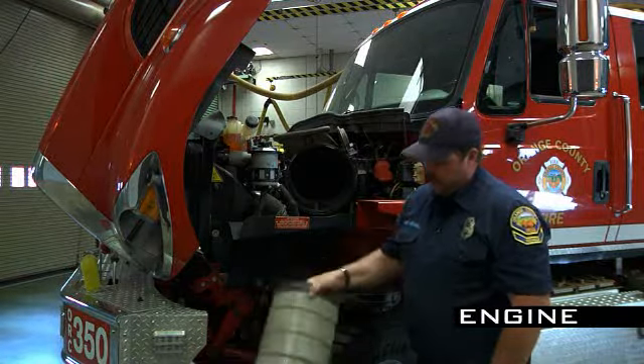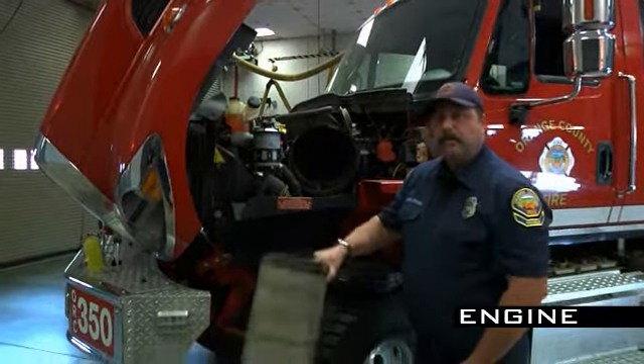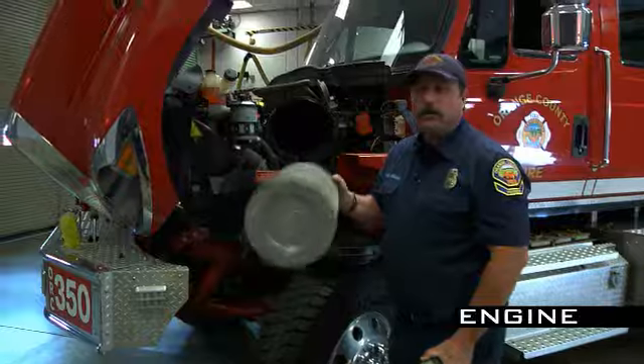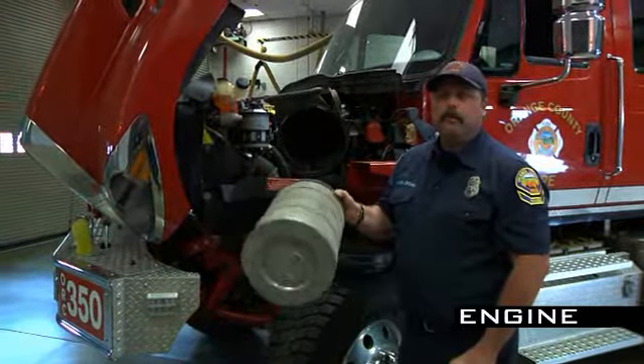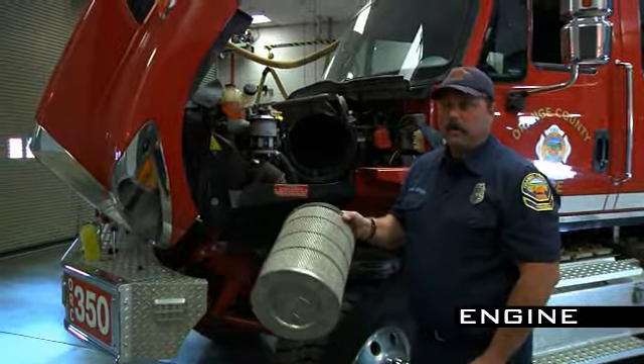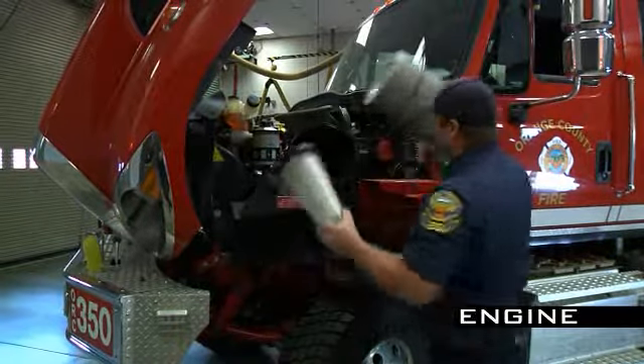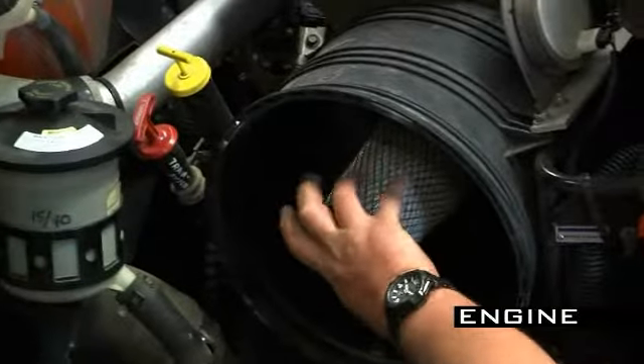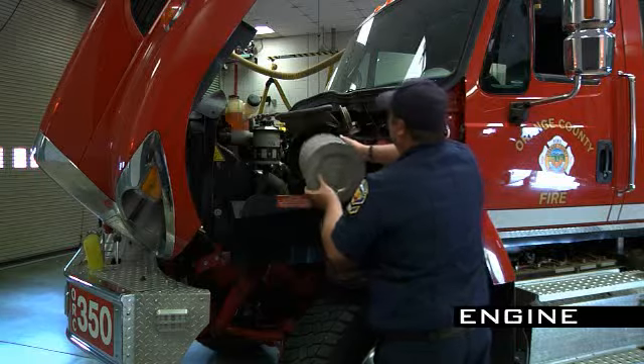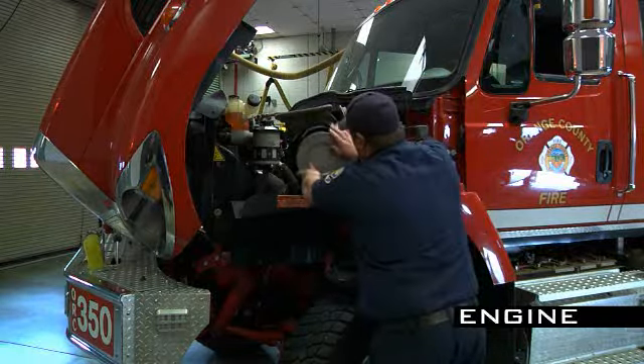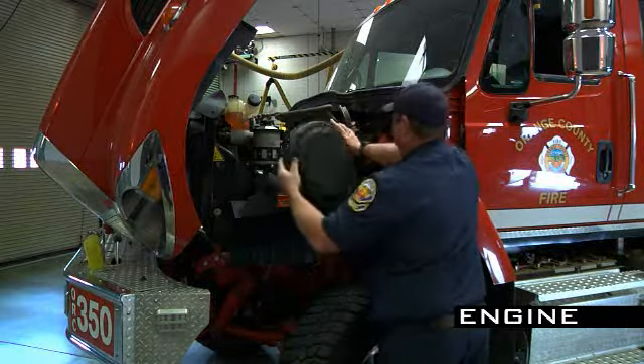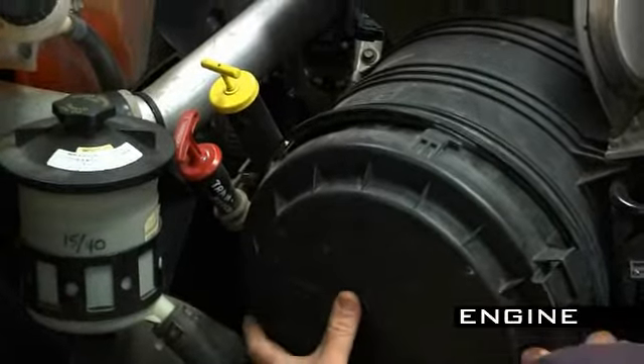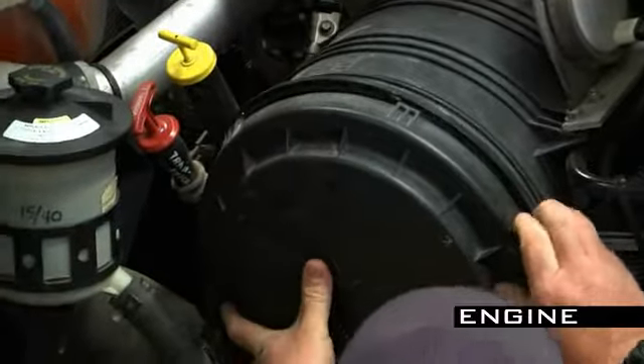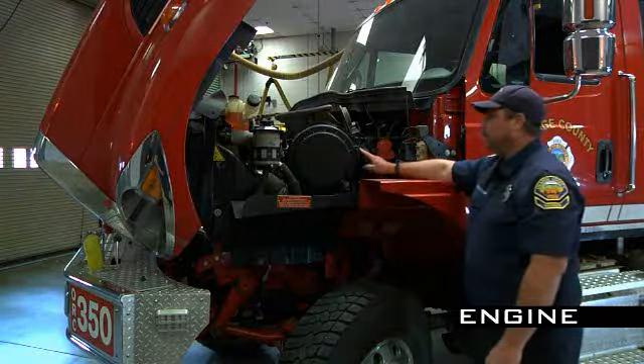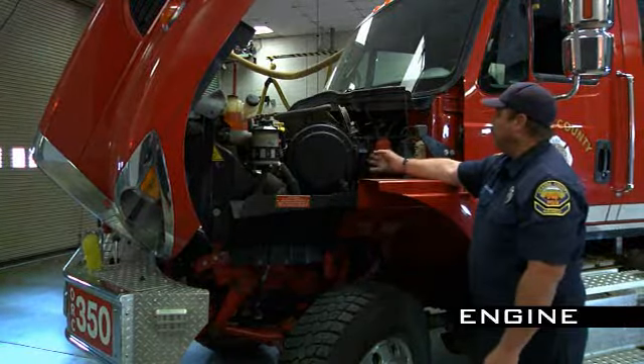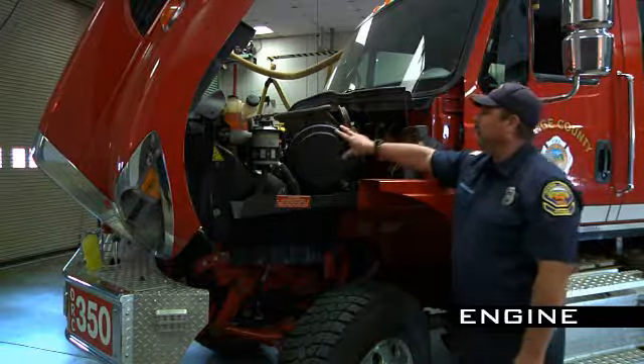The simplest thing to do is just tap it out, try to clean it out every day. We discourage you from using compressed air to prevent the paper element from getting torn. To replace it, it's quite simple. You just place the cone filter in. You take the primary filter after it's been cleaned, put it back inside, line up the tabs, rotate, and you'll hear it click. If you need light here in the work area, there's a work light switch that just focuses on this area.